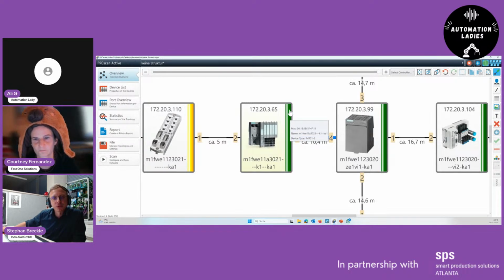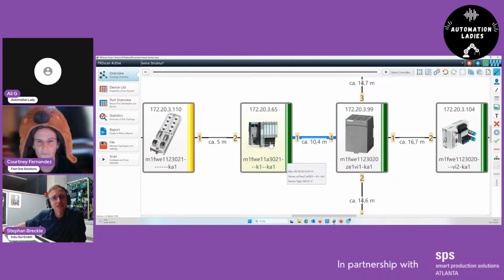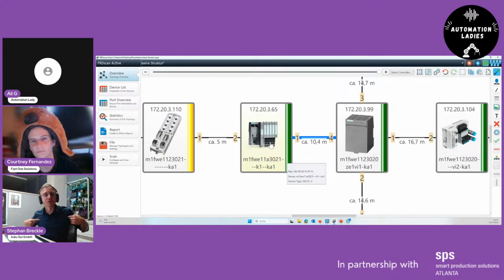From the inspector's point of view, from the PROFINET point of view, this device is completely fine, and also from the PLC's point of view this device is completely fine. So all devices tell you everything is good, but at the same time you get information that this device is overloaded and discarding data. Now the question is why, and the reason is simple: this device, like all Ethernet devices, is very smart - before discarding its own information, it discards the information that simply passes through.